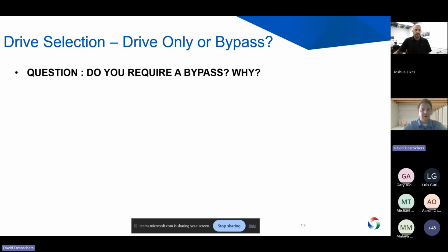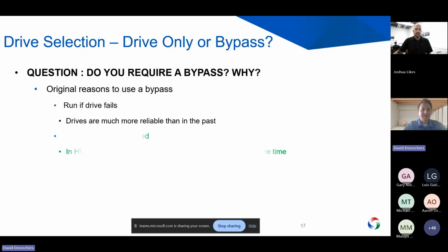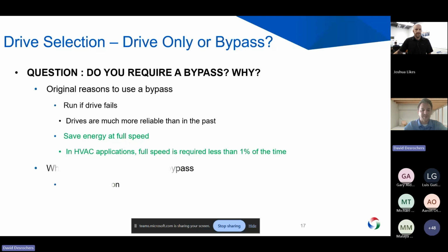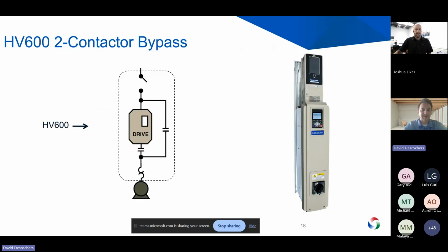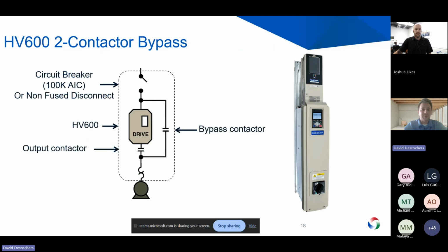So the question should be, do you require a bypass? Is it called out in your spec, usually, or your schedule. The bypass is basically going to, like the name says, bypass the drive. So rather than running power through the drive to run your motor, we give you the option to switch over to this bypass contactor. In real time, you can press the bypass button and the drive will shift off of running the motor directly through the VFD and will instead close this bypass contactor on the right and actually run power directly to the motor.